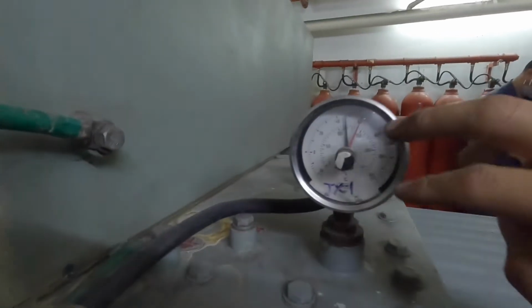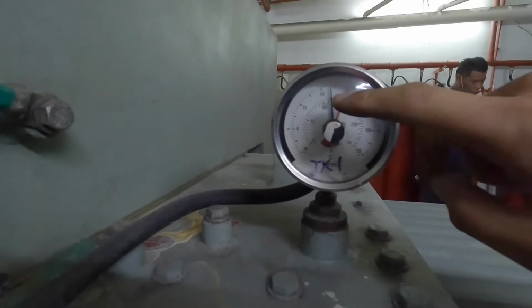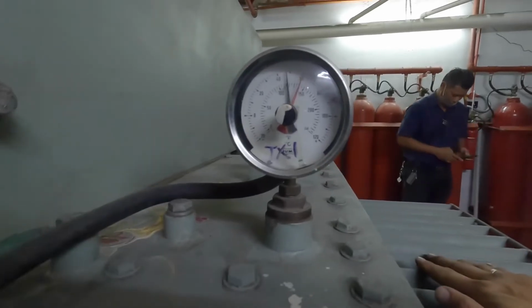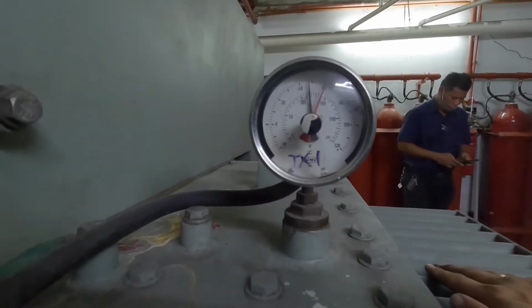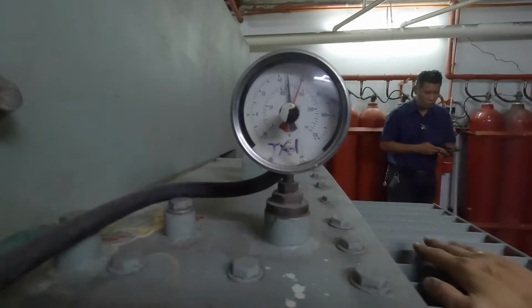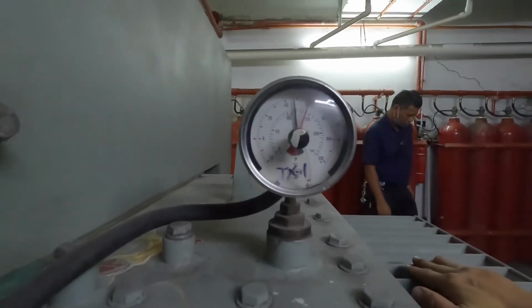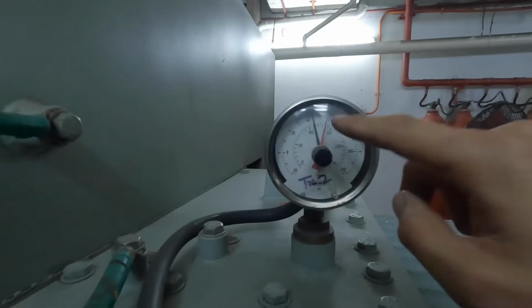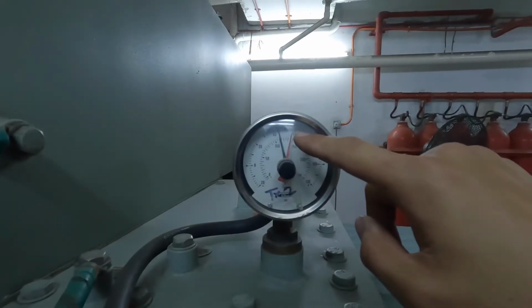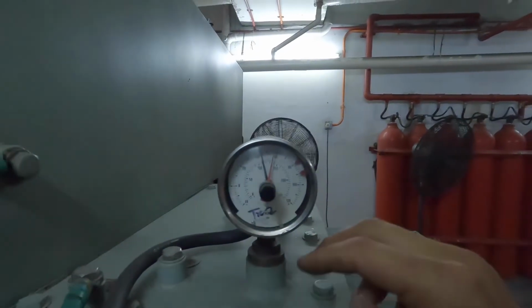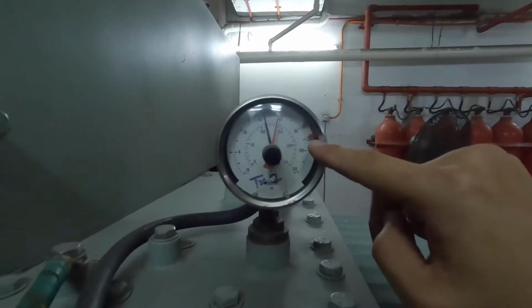Okay, here we have a transformer, two Onan transformers. Okay, here we have the temperature. Okay, in good condition. Maximum temperature is about 60 degrees Celsius. Then the current temperature is just below 50. Okay, no problem. It's in good condition. And then there's another transformer here, transformer number 2. Current temperature is about 45 and maximum is about 60. The alarm is 80, the tripping is 90.